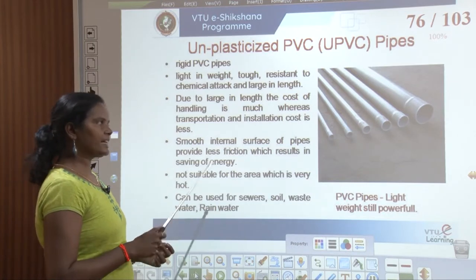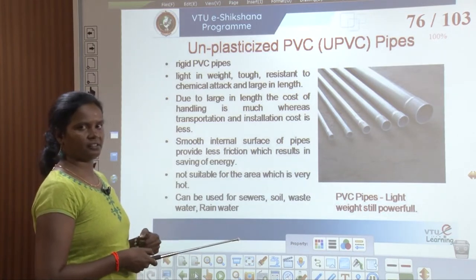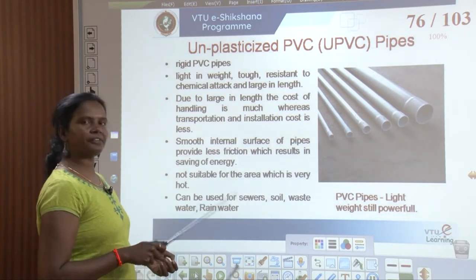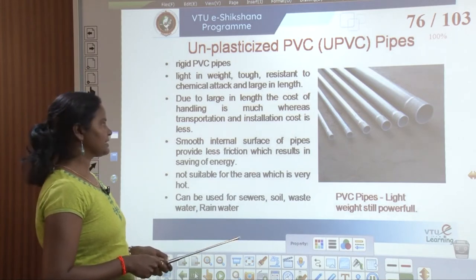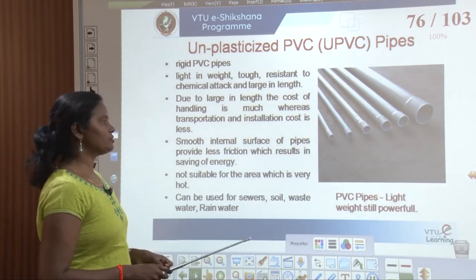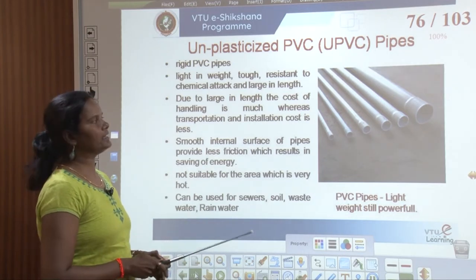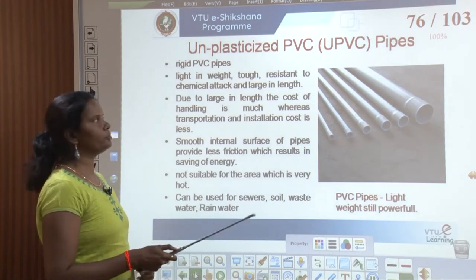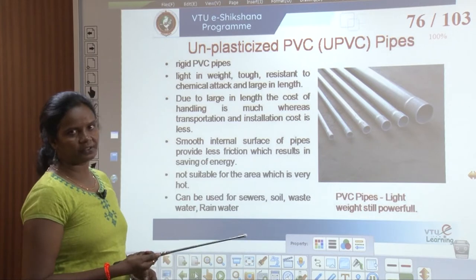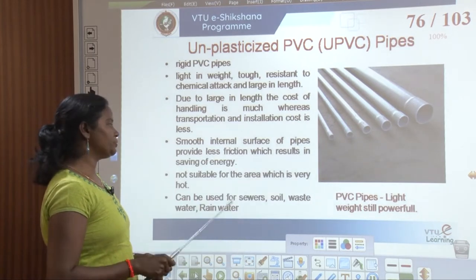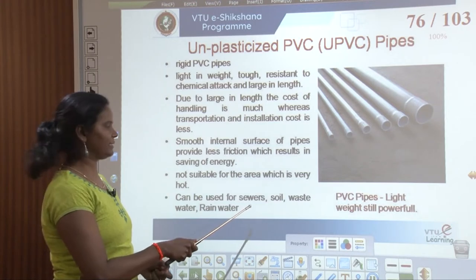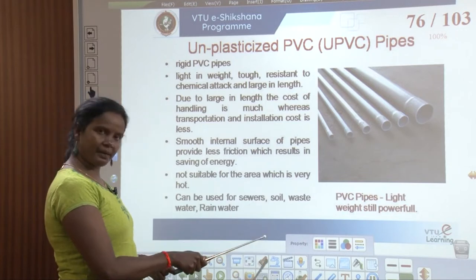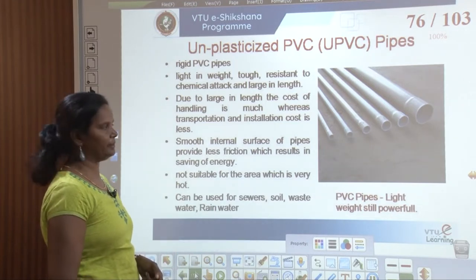UPVC pipes have a very smooth internal surface, which results in less friction and saves energy. They are not suitable for hot water because the chemical composition of PVC pipes can react with hot water. They can be used for sewers, main sewers, soil pipes, waste pipes, and rainwater.